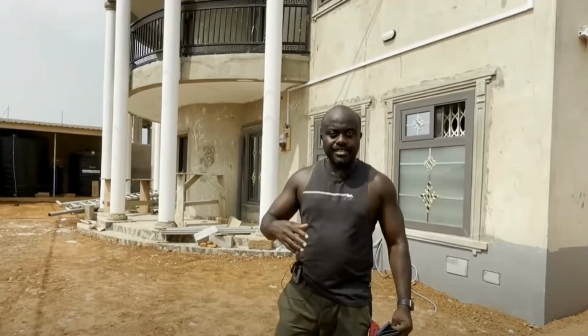If you remember how the back of our building looks, you can see the picture on your screen. We've got metallic balustrades which are not too far away from the electric cable. So if, in the unlikely event, those balustrades became live, and you were touching it at the same time, that would be a significant risk if they were not bonded to earth. Our balustrades are connected to the rebars within the structure, and the rebar is connected to earth, so it's all at the same potential and safe.